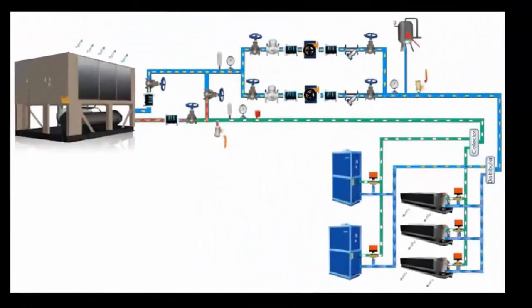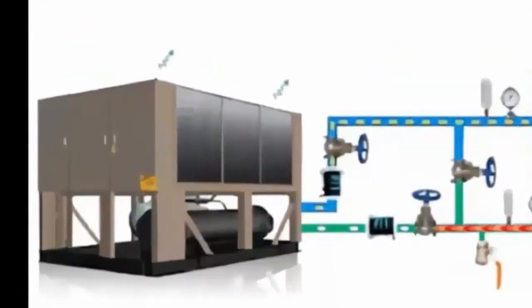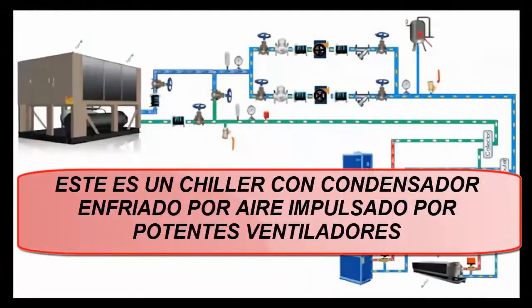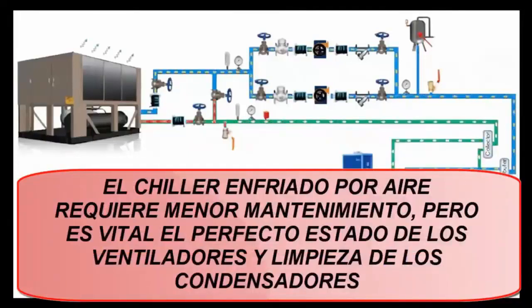17. As we are seeing in the animation, we have a chiller with an air-cooled condenser. 18. Let us remember that this type of machine is usually used in applications with low and medium thermal loads. 19. Although this type of chiller is less efficient than the one with a water-cooled condenser, it has the advantage of requiring little maintenance and a simpler installation or piping circuit.